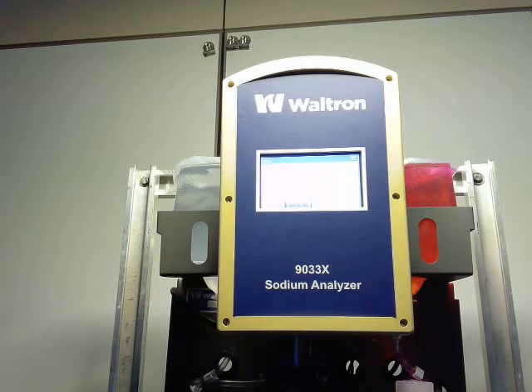With the cal fail, if it fails and we're on the low side of that slope, less than 83, typically that means our response is not enough, and usually that's a measuring electrode issue. One thing we talked about in the maintenance before was this regen solution. It's an acid solution. It etches away the top layer of glass and opens up the membranes of that probe again. So as our electrode ages, that can certainly help bring the electrode back to life, and then we can recal and hopefully get a passing calibration.